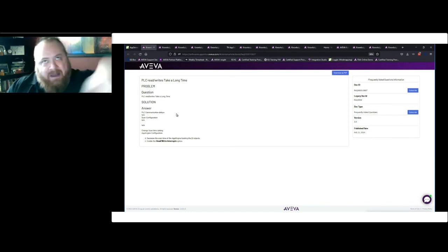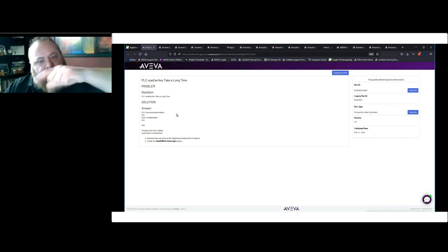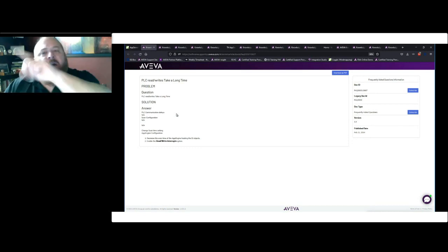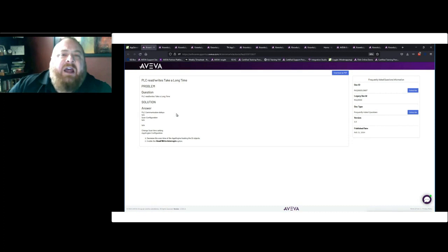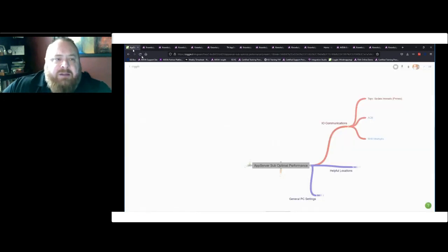So the net effect of that is if you think back to the circle where the clock on the wall, where I'm reading inputs, doing my housekeeping, writing outputs, reading queued inputs, there's these message pumps that get put in here that sort of inject I/O out to field devices. So what that allows us to do is be interrupt driven with our I/O instead of having to do it once per scan. And it's configurable. When you turn it on, I want to say that by default, you get 5 and you can tune it.